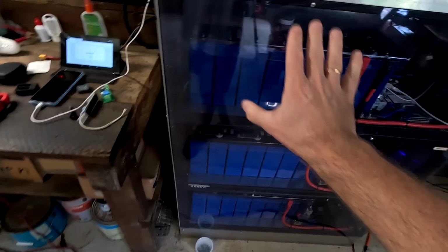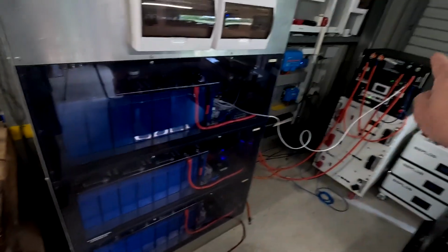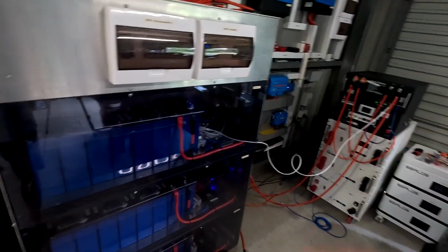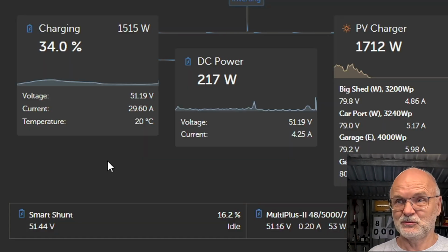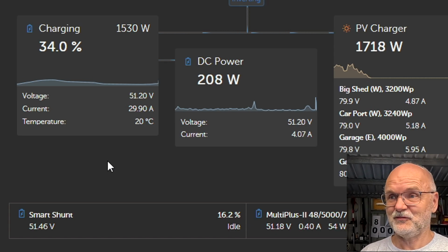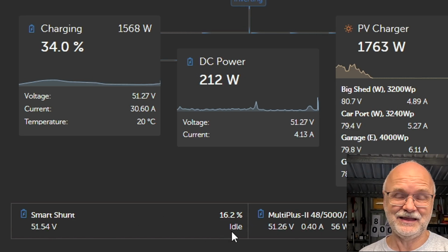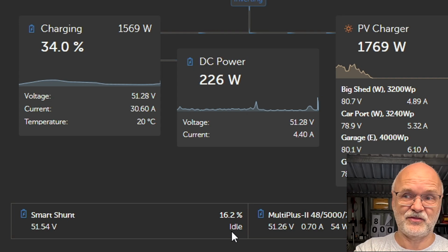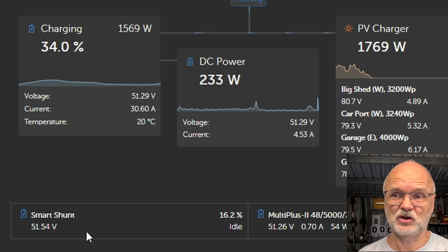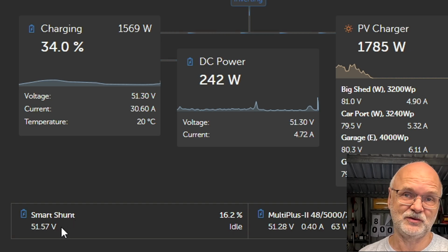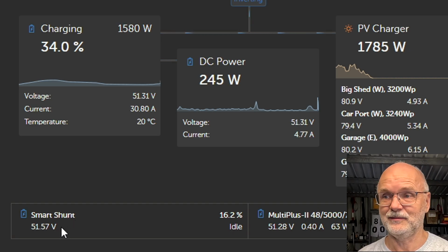I'm just turning off all 3 battery banks. So they are completely disconnected, isolated. We are only running the whole show now from these 2 batteries. And we are charging with 29 amps now into these 2 batteries. The smart shunt is idling because there's no current going into these other 3 batteries anymore. It only shows us the percentage now, the state of charge, and the voltage it measures. But there's no current going in anymore.